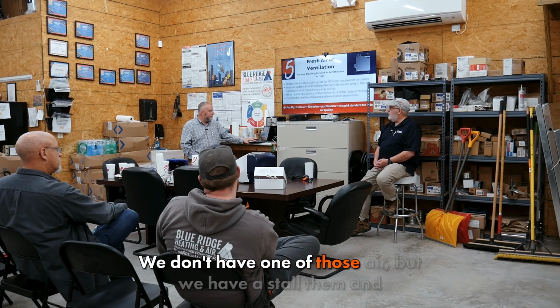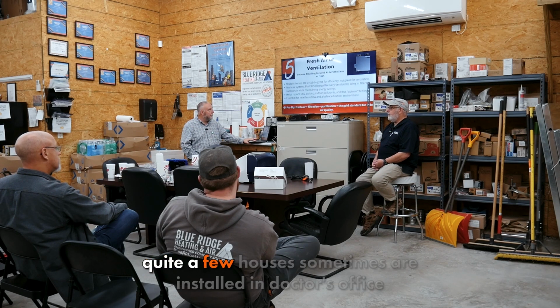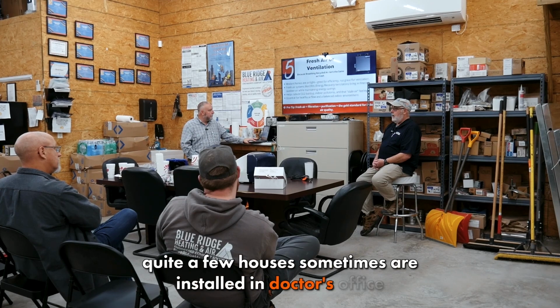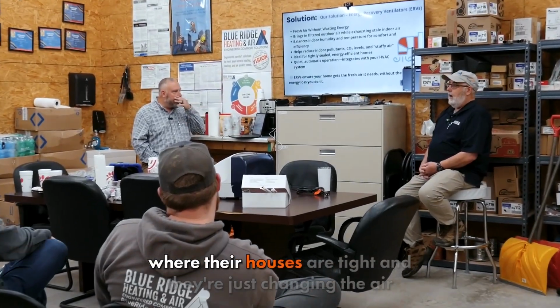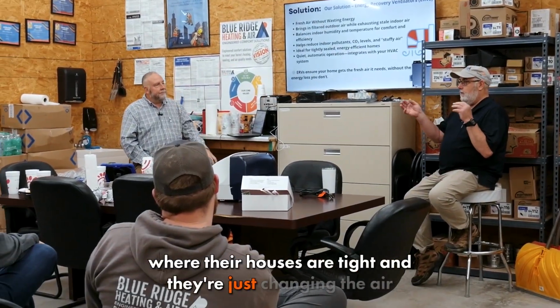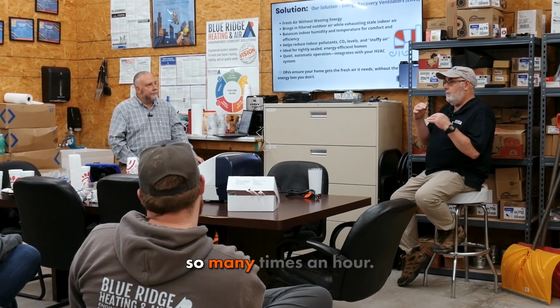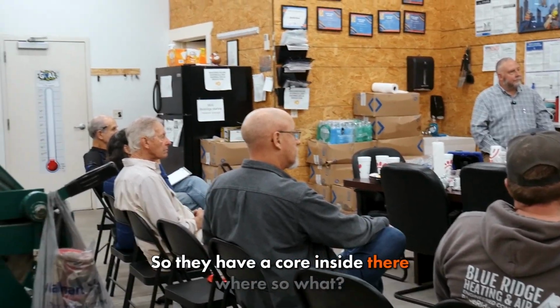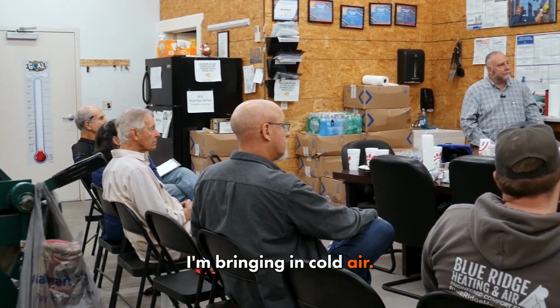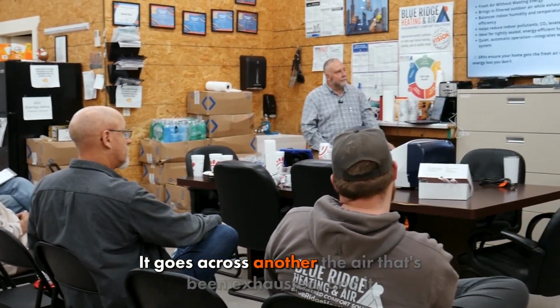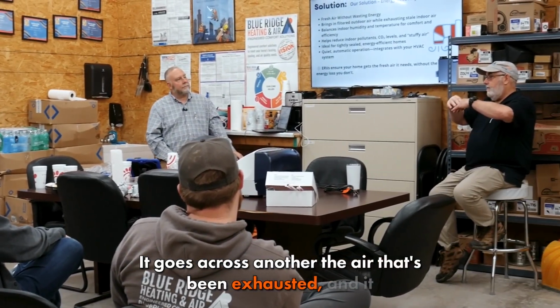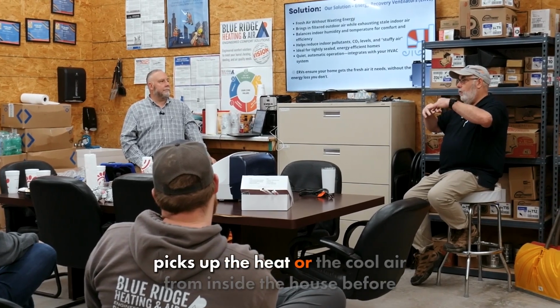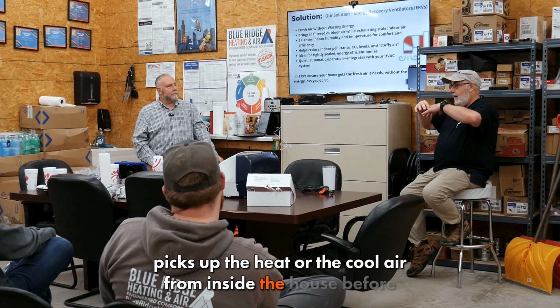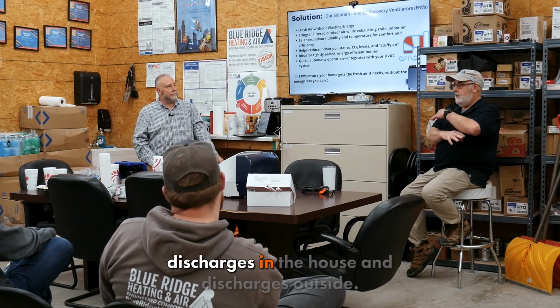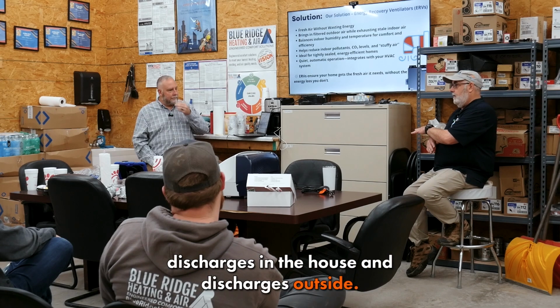We don't have one of those there, but we've installed them in quite a few houses, sometimes in doctor's offices where the houses are tight and they're just changing the air so many times an hour. They have a core inside where, when I'm bringing in cold air, it goes across the air being exhausted and picks up the heat or cool air from inside the house before it discharges.